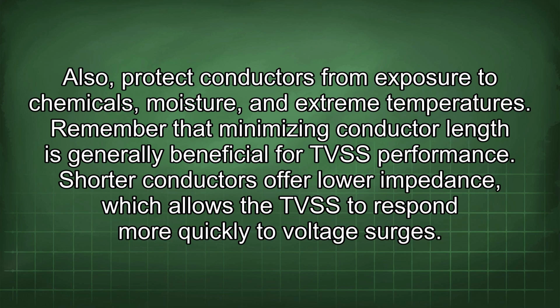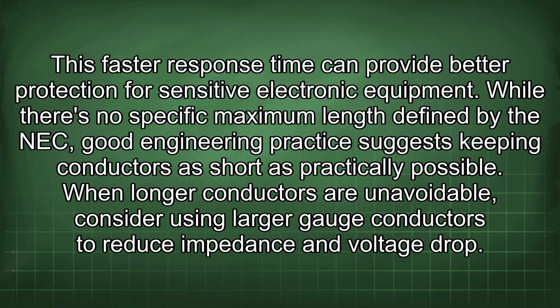Remember that minimizing conductor length is generally beneficial for TVSS performance. Shorter conductors offer lower impedance, which allows the TVSS to respond more quickly to voltage surges. This faster response time can provide better protection for sensitive electronic equipment. While there is no specific maximum length defined by the NEC, good engineering practice suggests keeping conductors as short as practically possible. When longer conductors are unavoidable, consider using larger gauge conductors to reduce impedance and voltage drop.